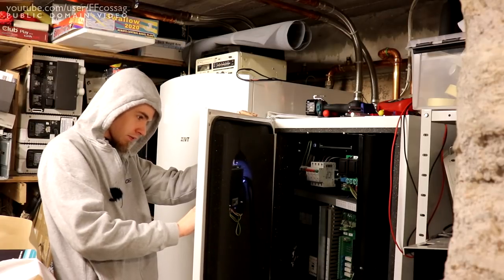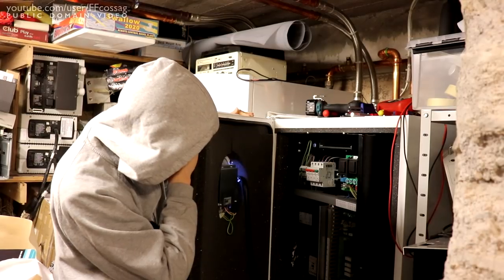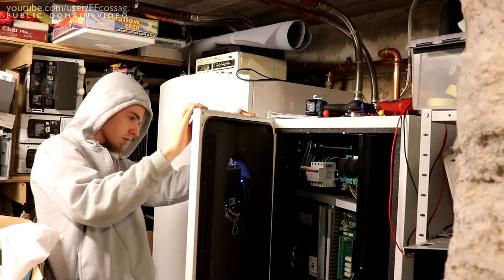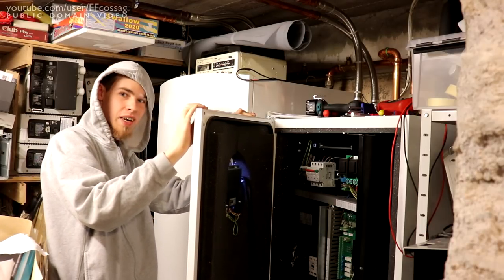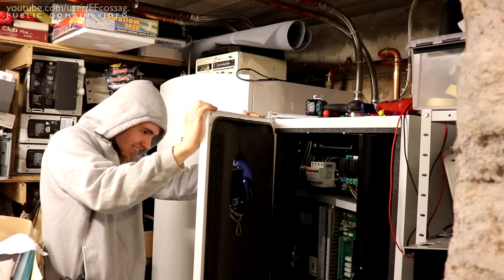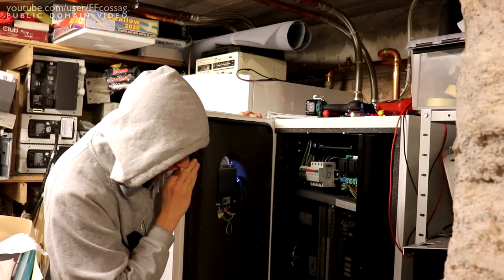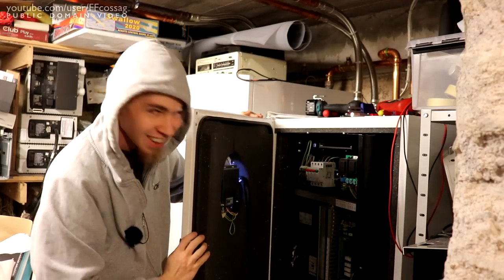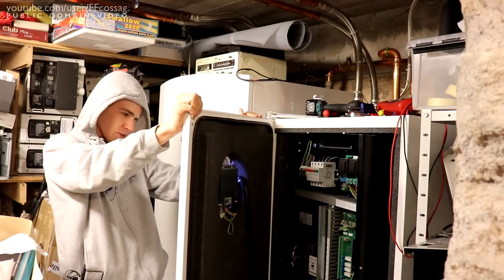It's doing something. It's on! Listen to that VFD, we've got revs, we've got revs! It's working, it's not gone on fire. The compressor's running. We have revs, I can't believe it, 1440 RPM.